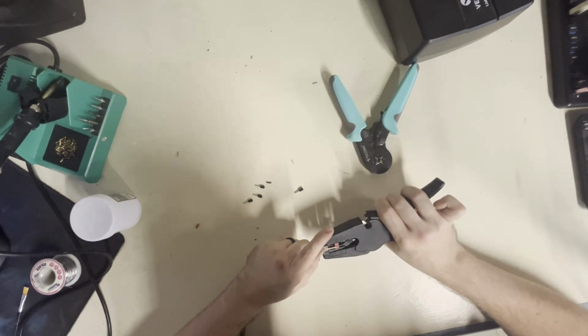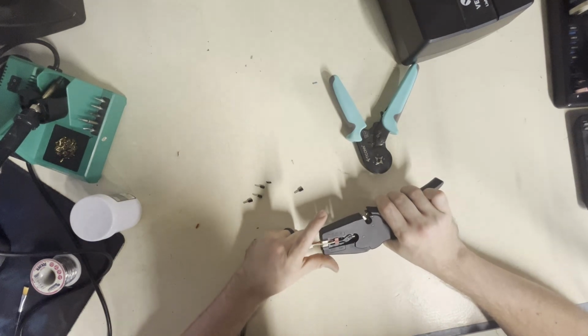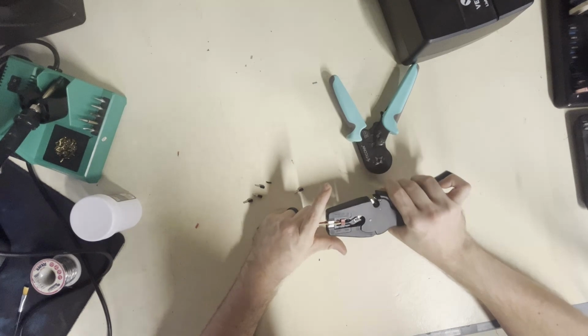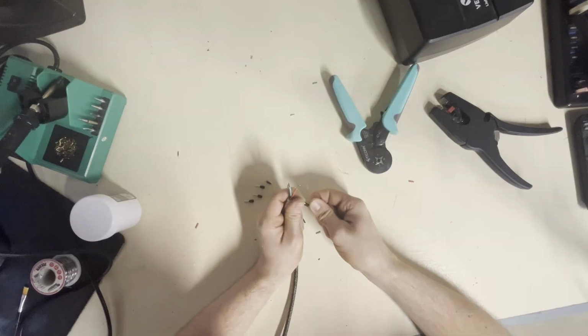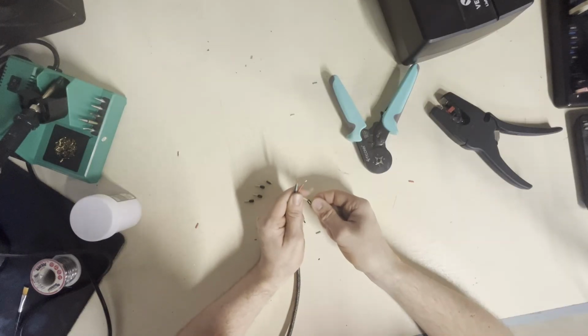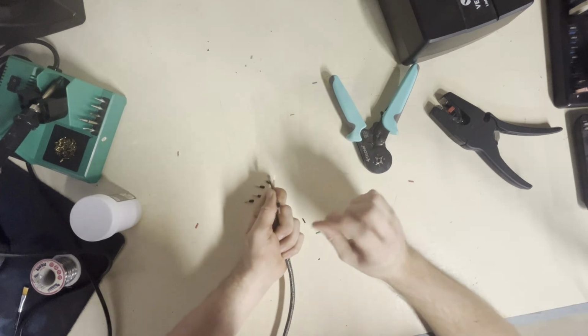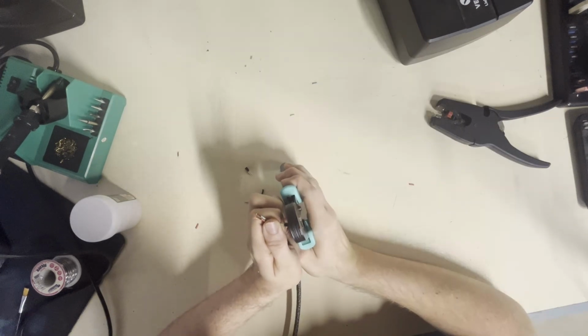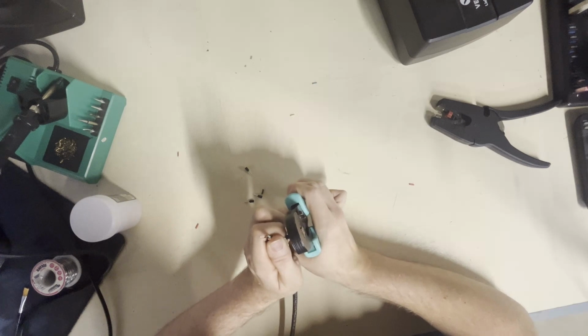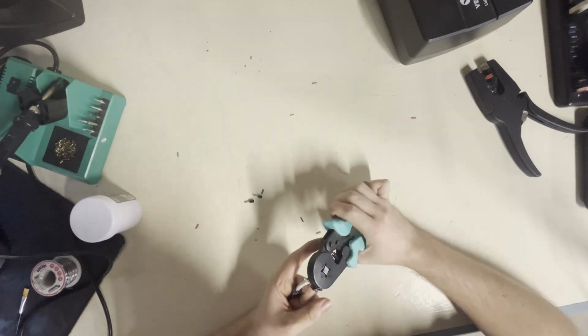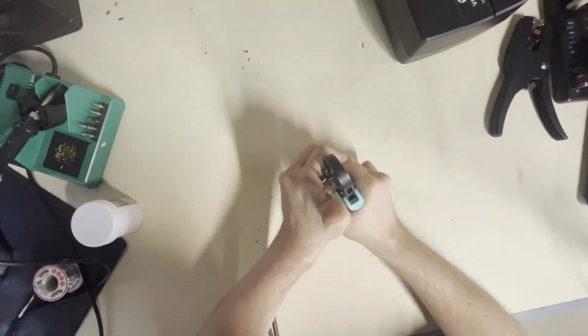In order to use the ferrule crimps, we are first going to strip the wires and then give a little twist to the ends of the wire so we have no frayed ends. We are then going to slide the crimp on. Using the crimping tool, we are going to crimp the metal half. And I have to do this 3 more times for this group of wires, and even more for the rest.